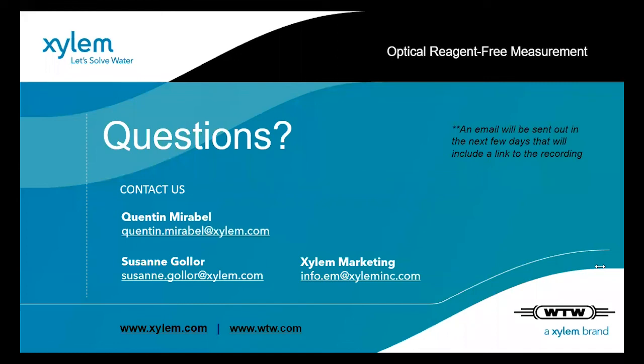Yes - calibration means adapting the method to your environment. This is done by taking the same sample you'd measure directly with the optical method, and also running it through a reference test kit, like a COD cell test, or eventually for nitrate and nitrite using reagent test kits as well. That's the reference, that's the calibration. Once it's set, you can use it for a while - depending on your conditions, possibly longer if they remain very steady.